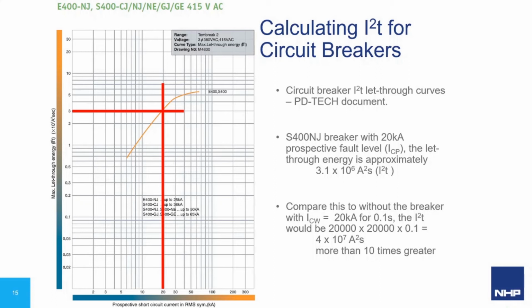The way we do this is we can compare what the energy let through of our circuit breaker is to the equipment in our board. So just like when we do our K²S calculation for our cable selection, we can do the same thing with our I²T of our assembly. This means even if our ICW rating is lower than the prospective fault current, we still can conceivably use the assembly provided careful selection of the upstream device.